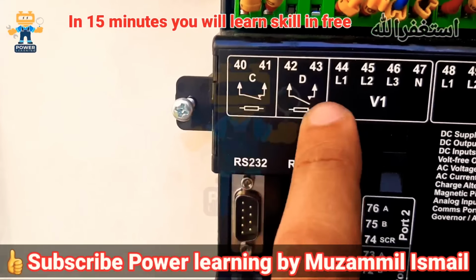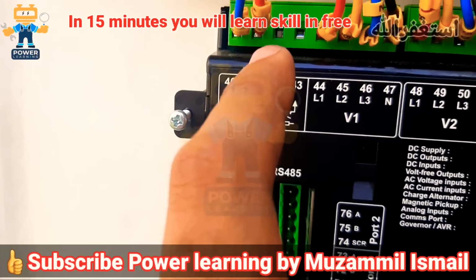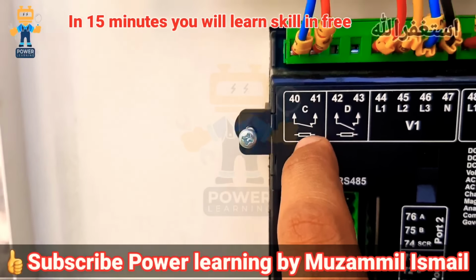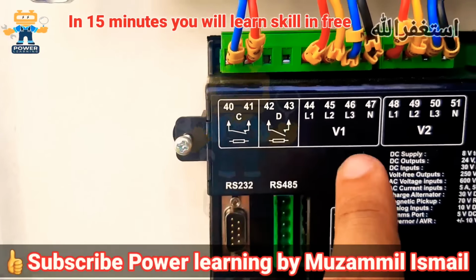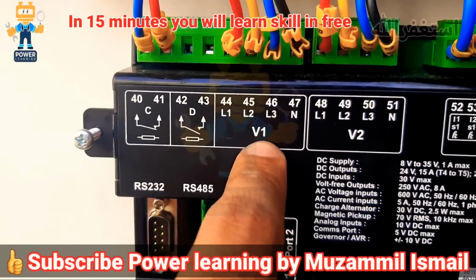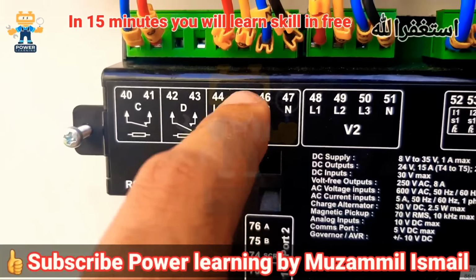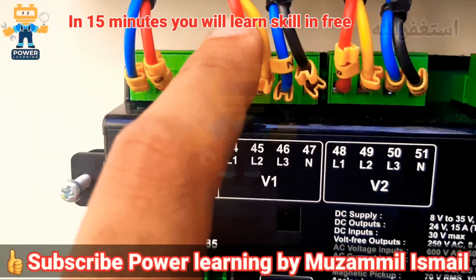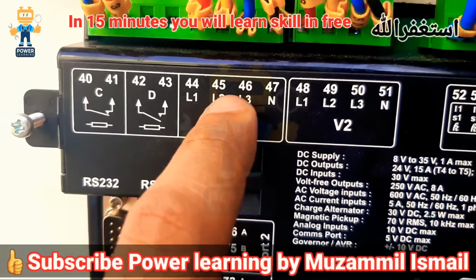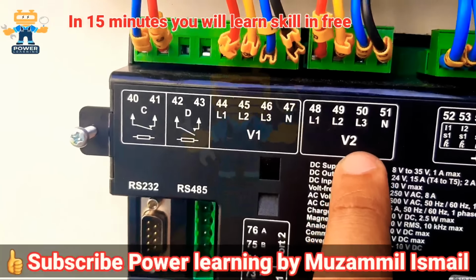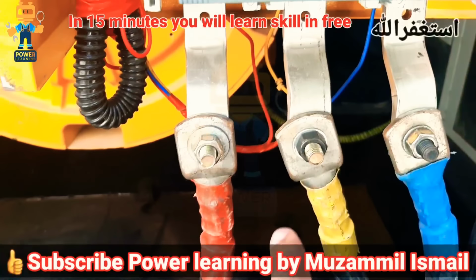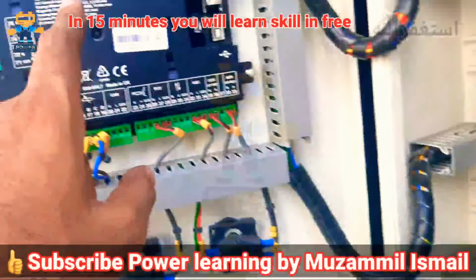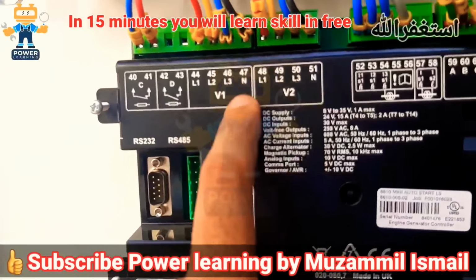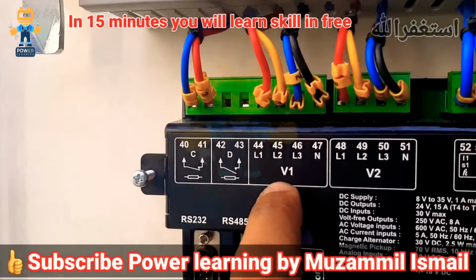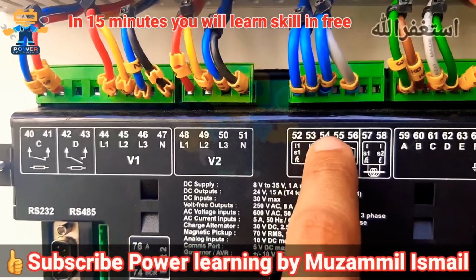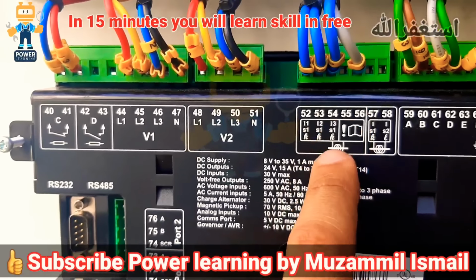So here these 4 contacts are volt free contacts. Here we have to connect our supply and then take it out as a relay, as a single pole relay. These are configurable. You can configure them from the PC. Here we have V1. What is V1? V1 is our generator supply on which this controller is installed. It is sensing this generator voltage on V1. Here we are sensing red phase, yellow phase, blue phase and black, so line 1, line 2, line 3 and neutral. After that, V2 we are sensing from our bus side. This is called our bus side. You see these cables are coming directly to V2. So these two are voltage sensing: one is bus sensing and one is generator voltage sensing. Clear? After that 52, 53, 54, 55 and 56, these all are terminals for our current transformer.